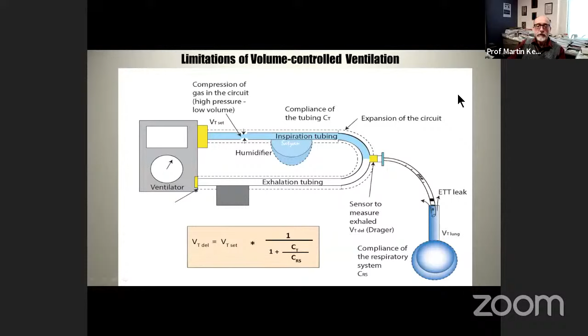So what we all resorted to was, of course, pressure-controlled intermittent mandatory ventilation, which in its basic functionality is nothing more than a mechanical T-piece resuscitator. There's continuous flow in the circuit. There's a PEEP valve maintaining certain distending pressure, and the expiratory valve is open. This is your T-piece, this is your thumb, this is your PEEP valve, and the patient can breathe in and out of the circuit as desired during the expiratory phase.